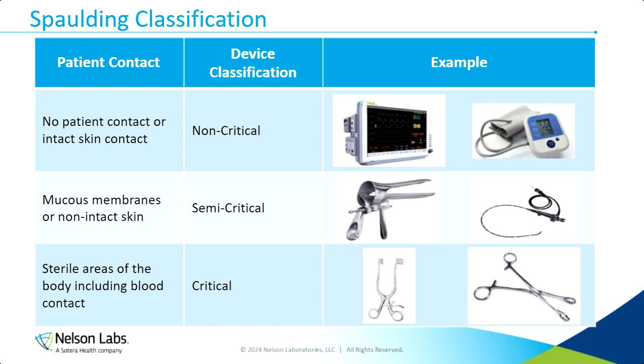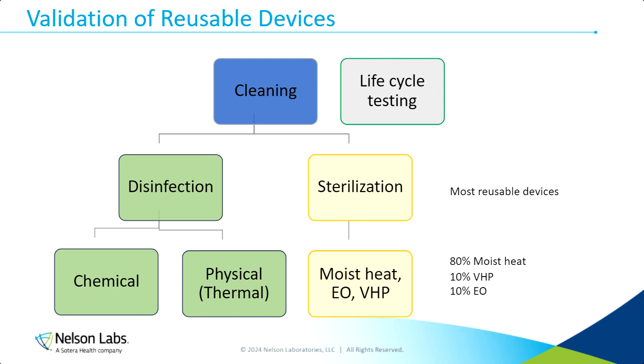So as mentioned, reusable devices need to be decontaminated between uses on patients. And what that means is that they need to go through appropriate cleaning and disinfection or sterilization procedures. Cleaning meaning the removal of visible contamination from the device, and then disinfection meaning the ability to achieve a specific log reduction based on the disinfection level you're trying to achieve, and then sterilization, achieving a certain sterility assurance level for your device. For disinfection, that process can either be through chemical or physical methods. And then sterilization will either be done through moist heat sterilization or ethylene oxide and VHP.